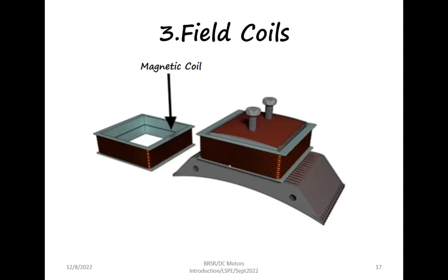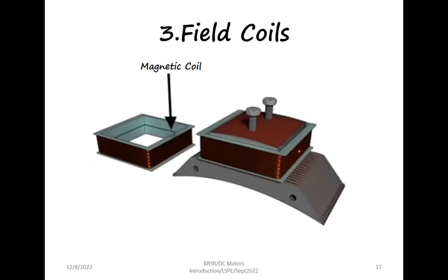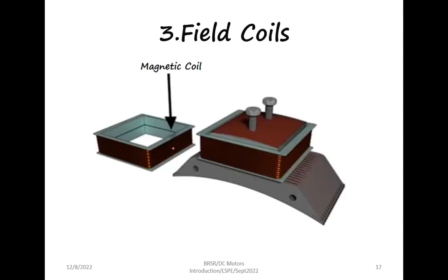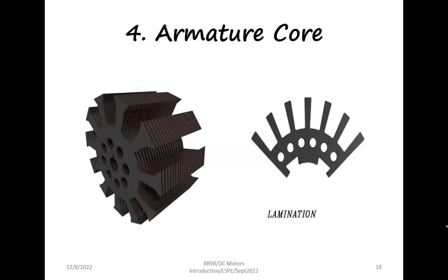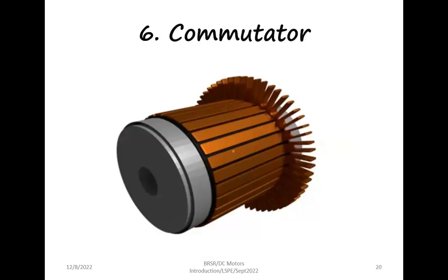There is a magnetic coil which is placed onto the pole core to become the field coil. So there is a pole core, a pole shoe, and surrounding the pole core you have the magnetic coil — this is the field circuit. The armature houses the conductors and also has a core. On the core there are slots in which the coil is going to be mounted. The armature core is also laminated — it is not a single solid piece but made up of a number of laminations. The winding is placed on the armature core.